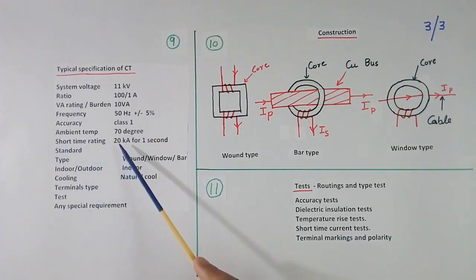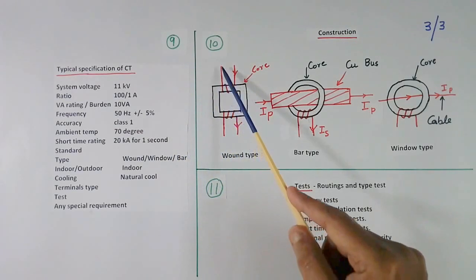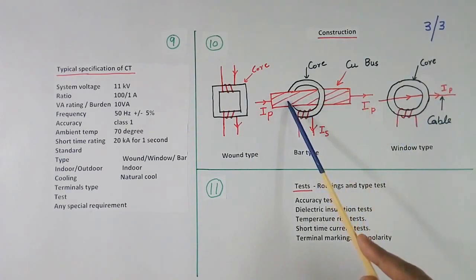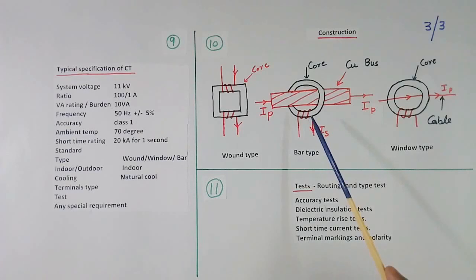Then short time rating, 20 kA per 1 second. What happens, if there is some short circuit or fault in the system, then heavy current flows. That heavy current will flow in this winding, primary winding. Our CT should not fail. So that CT should be able to take short time rating current. I have written 20 kA. However it may be something else also. Then standard. There are various standards available, Indian standard, international standard. We have to tell which standard will be followed.